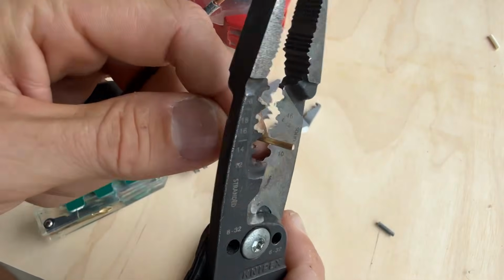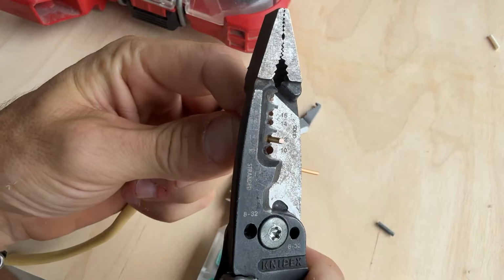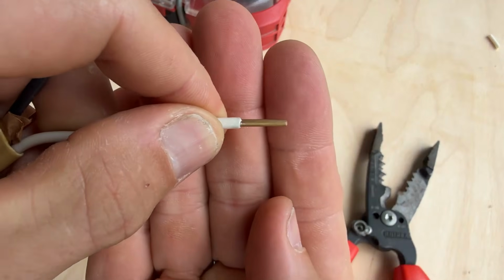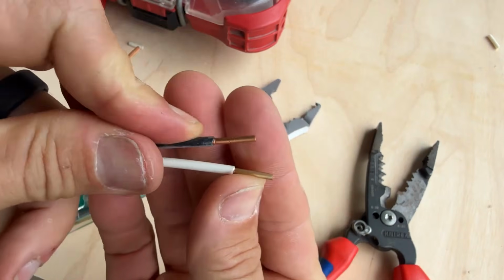But to be fair, let's go ahead and do that with the Knipex to see, and we have damage. So it will strip the wire, but it will also damage the wire. Not a great start, and know that when you damage the copper, that creates a hot spot and can be a future failure point for your wiring. That's why it's so critical to not damage your wire when you're stripping it.